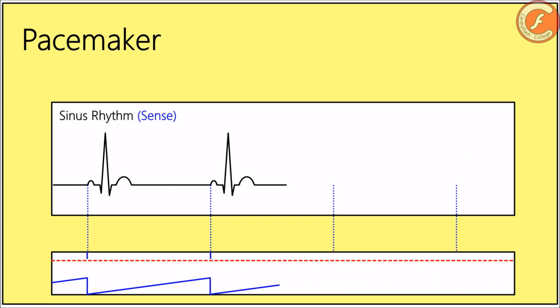Detection is also known as sensing and consists of recognizing the intrinsic electric activity of the heart. Using a series of algorithms, the device integrates that information, registers it, and determines if a bradyarrhythmia does or does not exist, treating it with a cardiac stimulation if necessary.